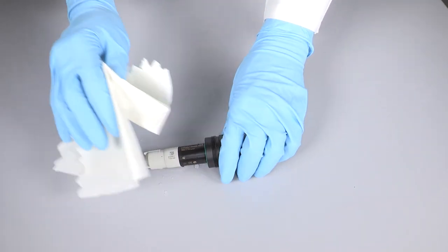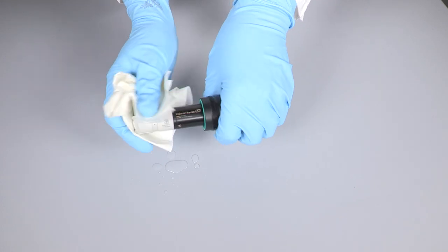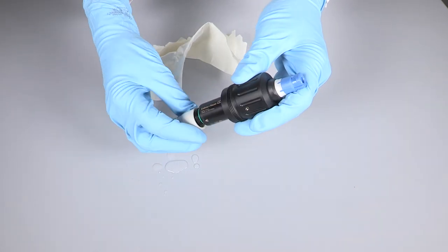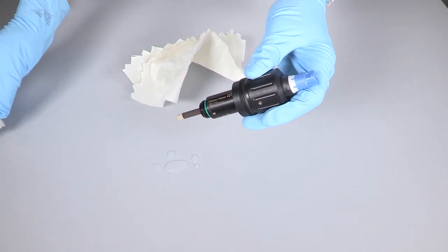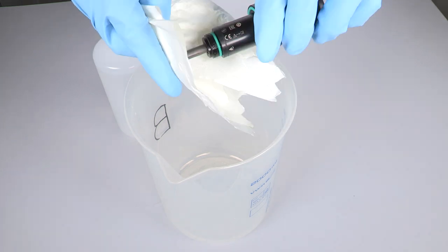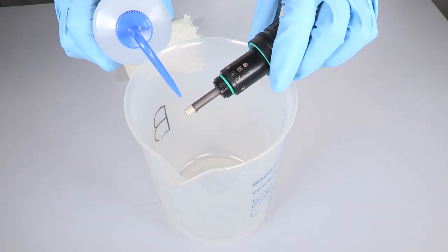Clean and dry the sensor and disassemble the membrane cap. Drain the old electrolyte and dispose the old membrane cap. Clean the gold electrode with a soft sponge and flush the electrode body with demineralized water.